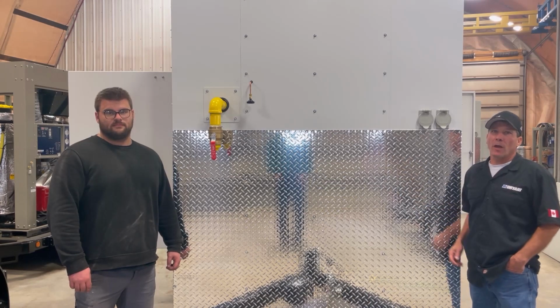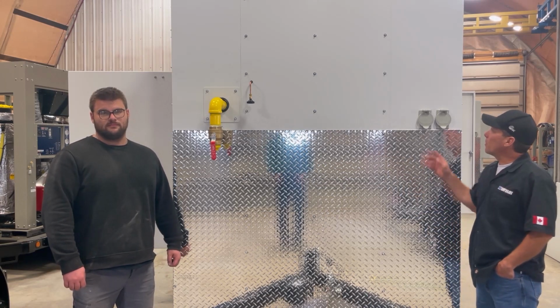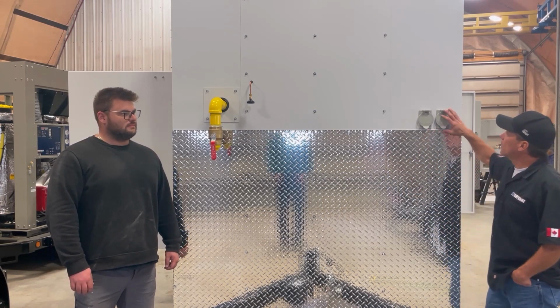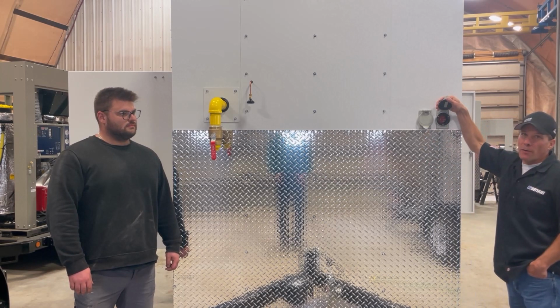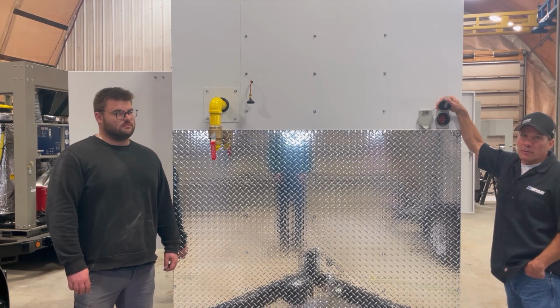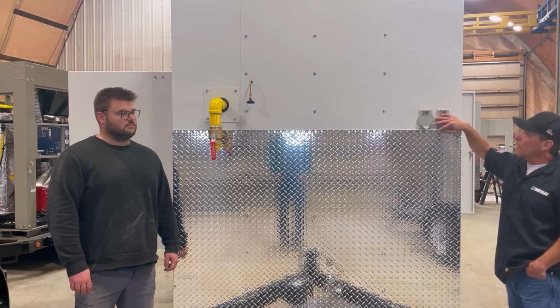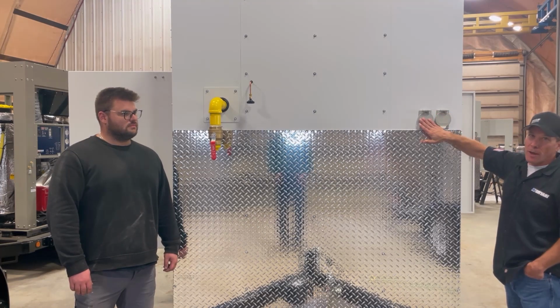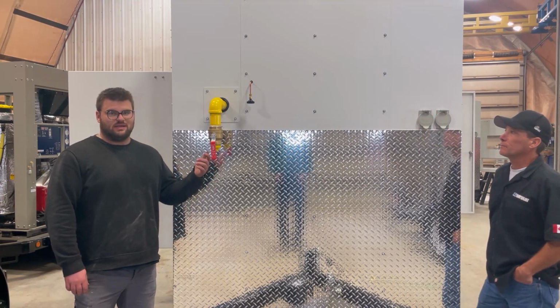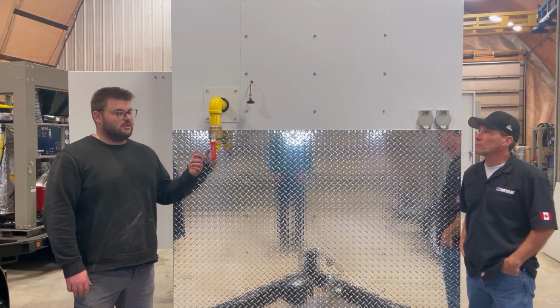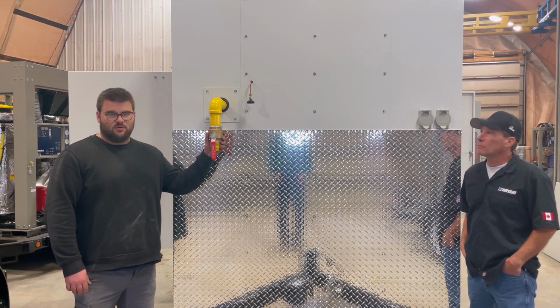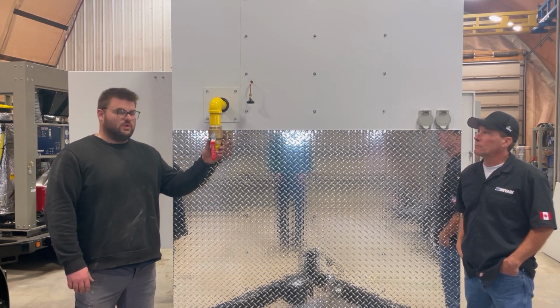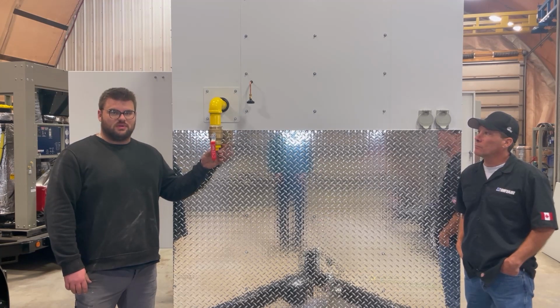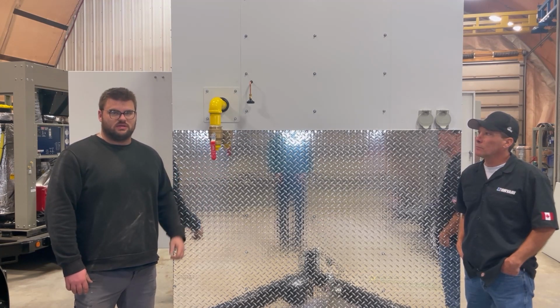Here we are in the front of the Hydro Heat Pro. We're going to talk about the electrical connections. Each one is 4-wire, 30 amp, single phase, 240 volts. You have this one for the front, this for the back. The gas line in is a 2-inch ball valve inlet. We use this for natural gas and propane. We have a regulator that's supplied with the unit that's stored inside the unit.